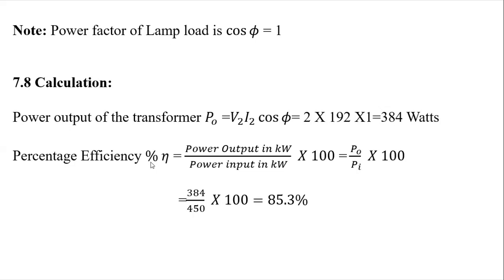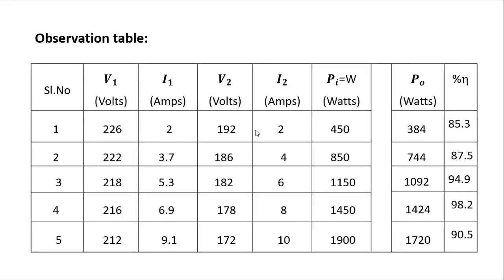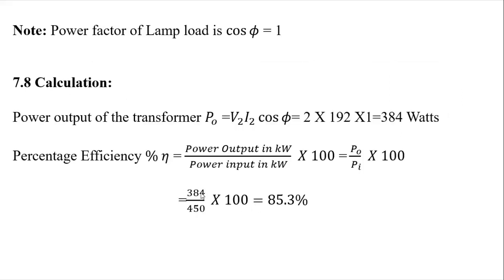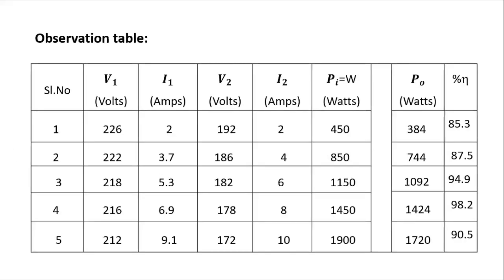Next, the percentage efficiency of the transformer is calculated as power output divided by power input into 100, that is P0 by Pi into 100. In this case, for the first reading, the power output of the transformer is 384 and the power input, from the direct wattmeter reading in the tabular column, is 450 watts. So 384 divided by 450 into 100 will give you about 85% efficiency. For every reading, we are going to calculate the efficiency of the transformer.